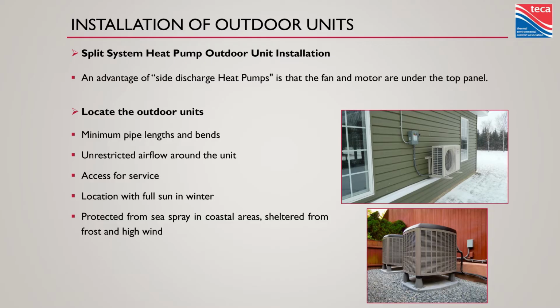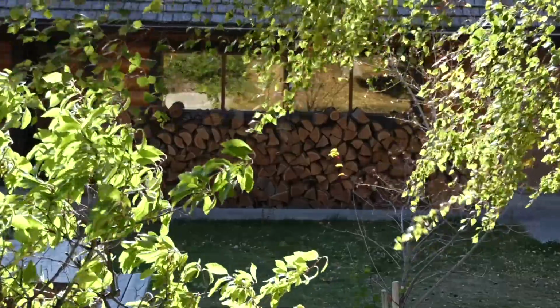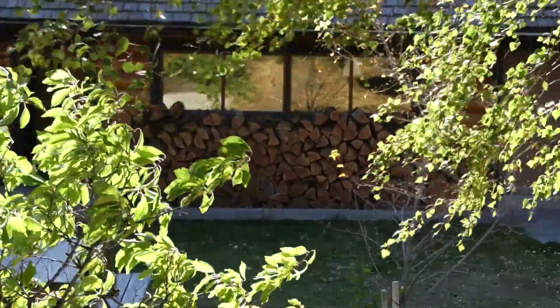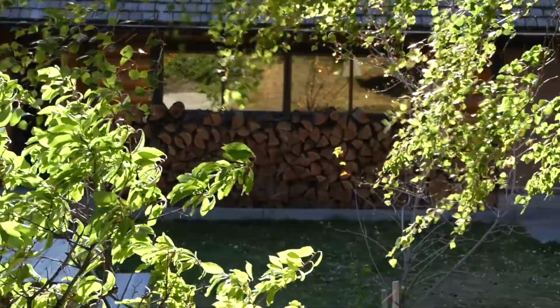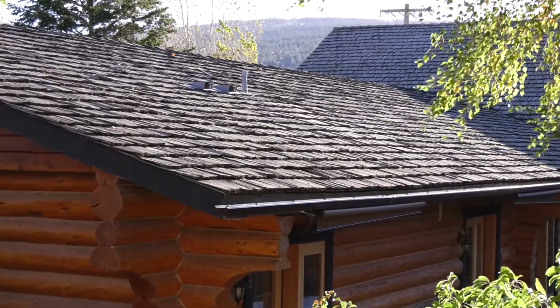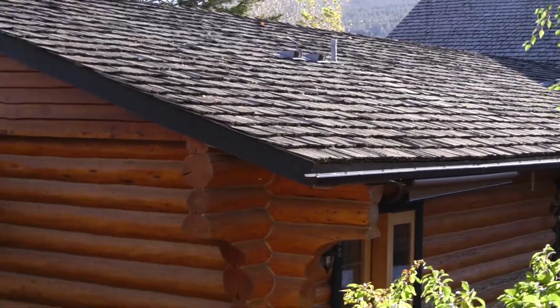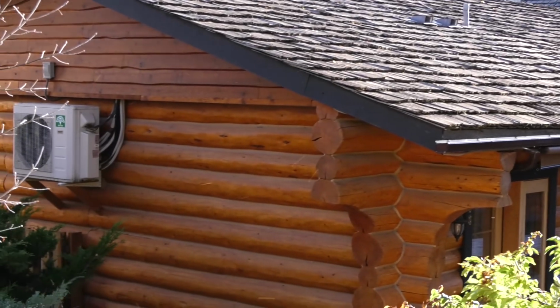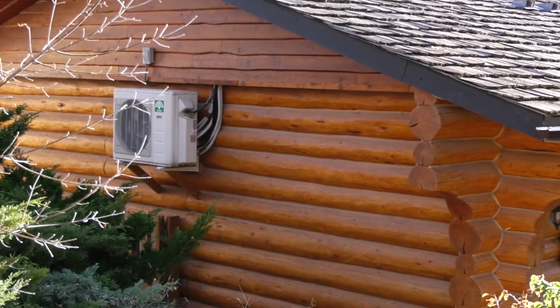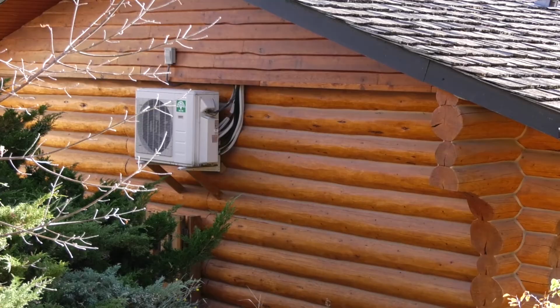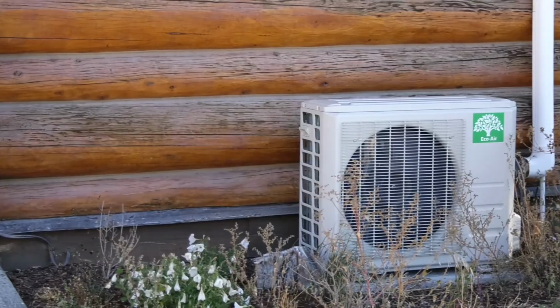Maybe it can be closer to a fence or a side yard if you're allowed to do that. None of these things are vastly different from each other. They're just orientations I want to familiarize you with. But you do want to minimize your pipe lengths, whether it's hydronic piping or refrigeration piping, the bends in that. You want to make sure these things are above the anticipated snow line so they're not just buried in a drift of snow. And you want to leave them access for service.